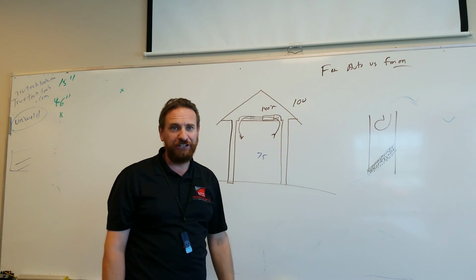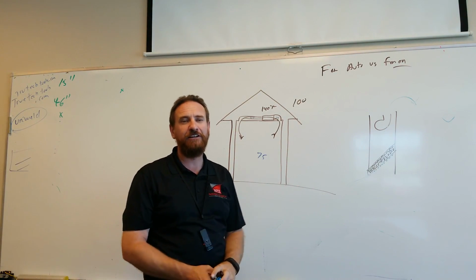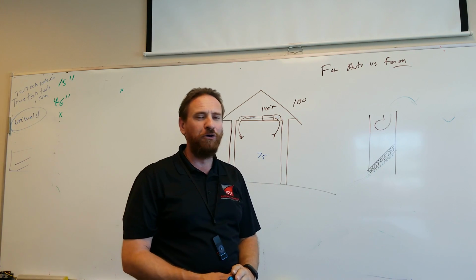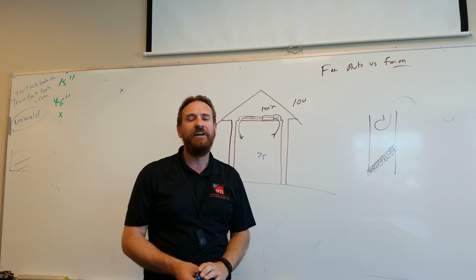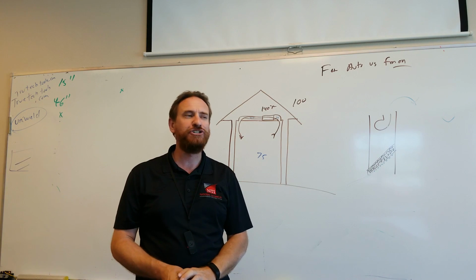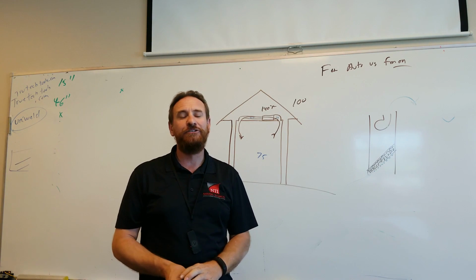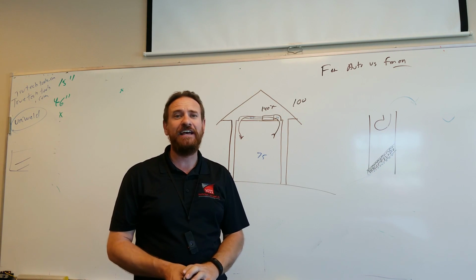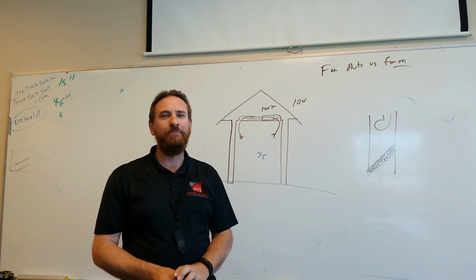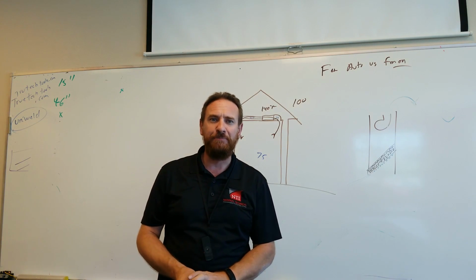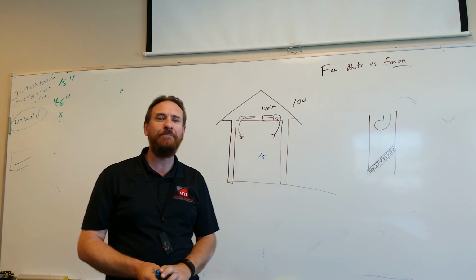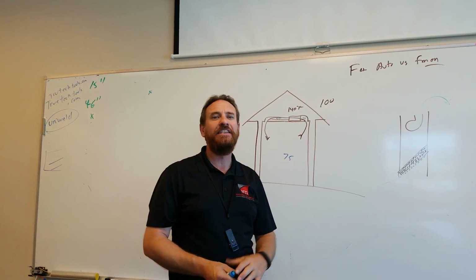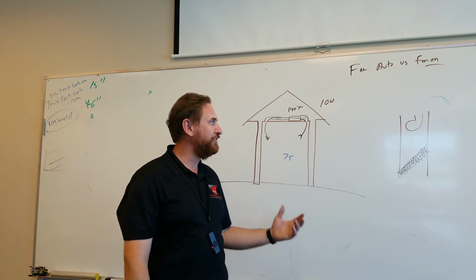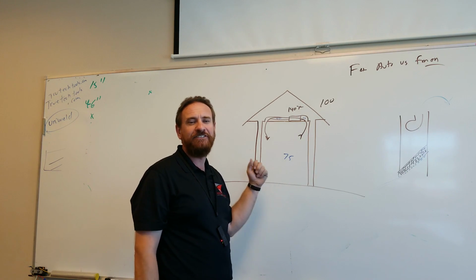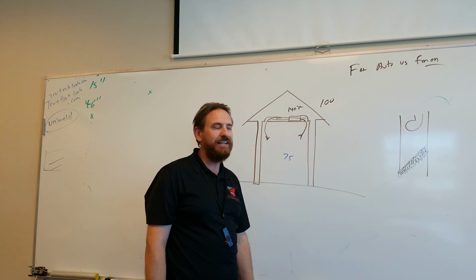On commercial buildings, you have a different rule set. Commercial systems have multiple compressors a lot of times. We have different built motors. Commercial buildings have a different design. So commercial buildings, I prefer to leave that unit running all the time. If that motor stays running, there's less wear and tear in the belts and the bearings, and it's better to keep that big unit running constantly than having it cycle on and off.